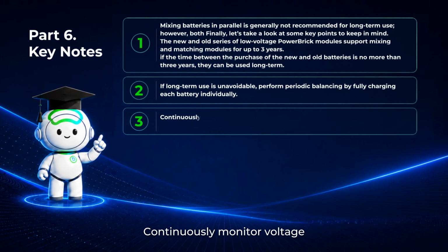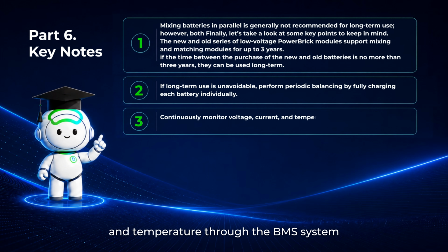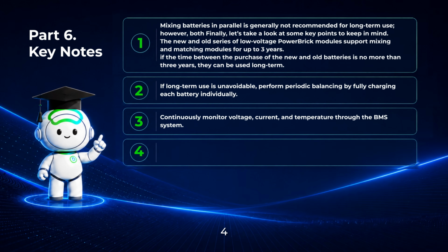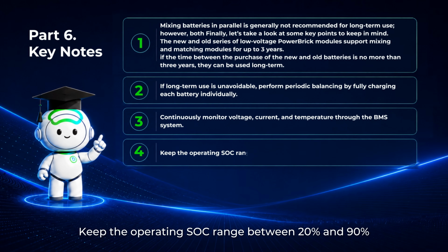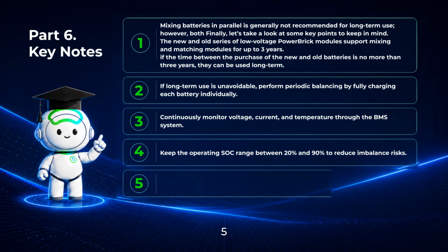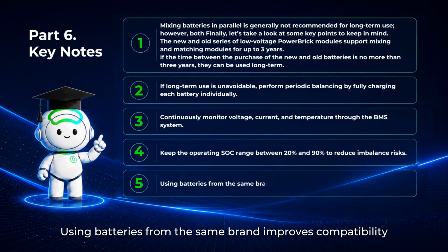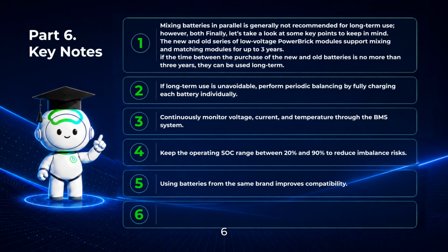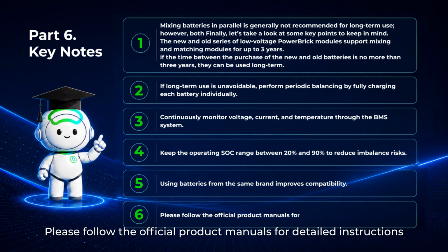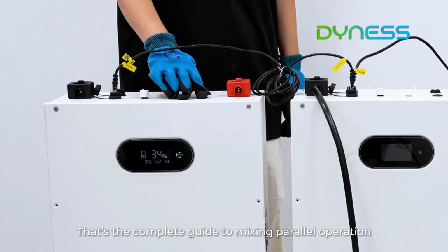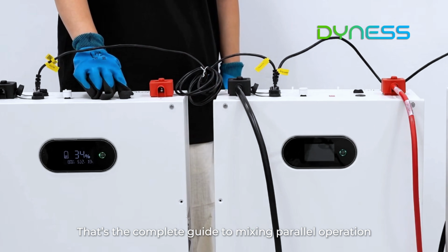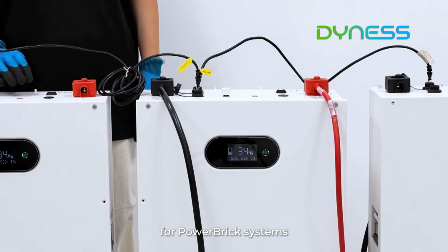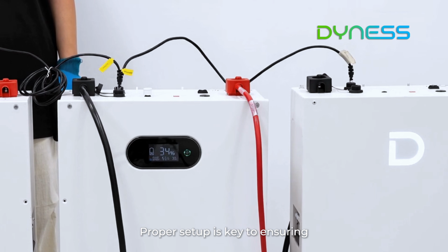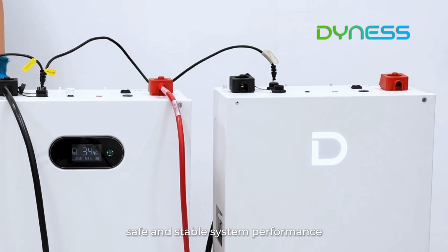3. Continuously monitor voltage, current, and temperature through the BMS system. 4. Keep the operating SOC range between 20% and 90% to reduce imbalance risks. 5. Using batteries from the same brand improves compatibility. 6. Please follow the official product manuals for detailed instructions. That's the complete guide to mixing parallel operation for PowerBrick systems. Proper setup is key to ensuring safe and stable system performance.